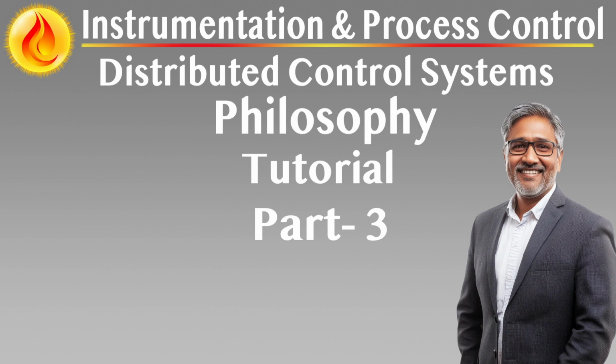Architecture and certified safety controllers. The FGS runs on a high reliability, certified PLC or Safety Instrumented System (SIS) with TMR or 1oo2D redundancy. All control logic is deterministic, real-time, and independently executed from the DCS. High-density smart I/O. Smart I/O modules with built-in diagnostics support digital and analog detectors, including flame, heat, smoke, IR/UV, H2S, and LEL gas detectors. Input loops are continuously monitored for open circuit, short circuit, and drift.